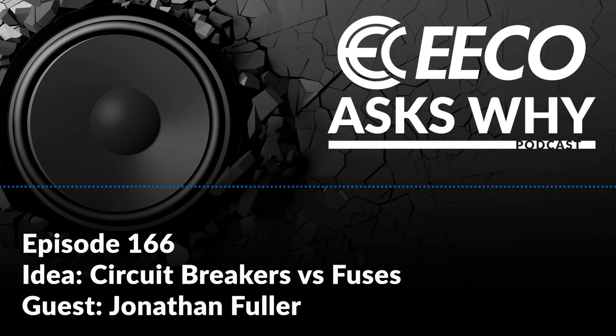Right. So let's talk fuses now. How do you select the proper rating of the fuse that I need for the application? That's a question, right? Like you mentioned earlier, there are so many different kinds of fuses: class L, class RK5, CC fuses, class J. There are all these different kinds of fuses for different applications, like drive fuses specifically for variable frequency drives, or fuses specifically for a motor. Depending on what kind of application you're using is going to determine what kind of fuse you want to use. Some of them blow a lot quicker than others. Some are called slow blow, so it takes them a little bit longer to break. So again, just like with circuit breakers, you want to make sure you're using the proper class fuse, designed for your application.